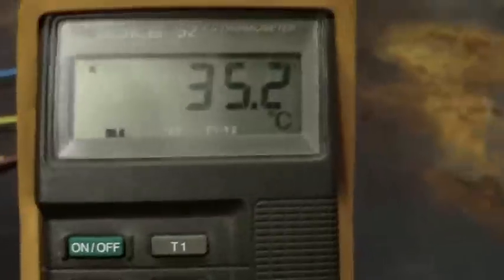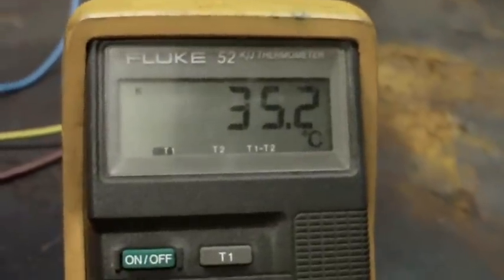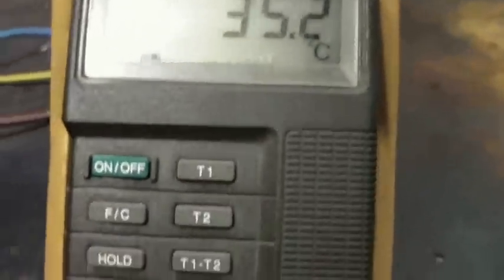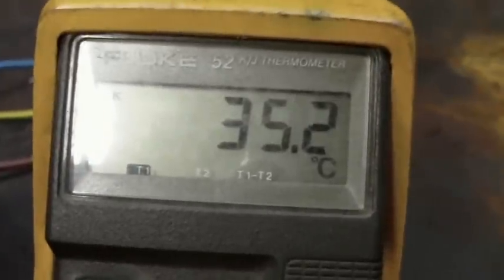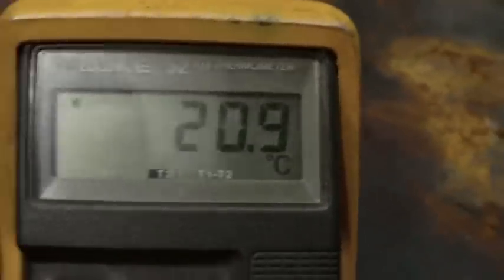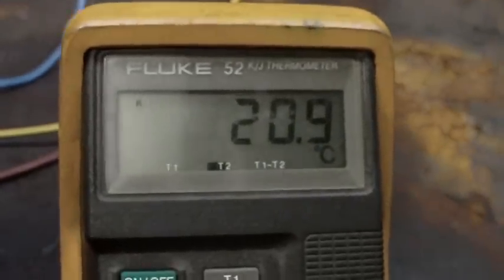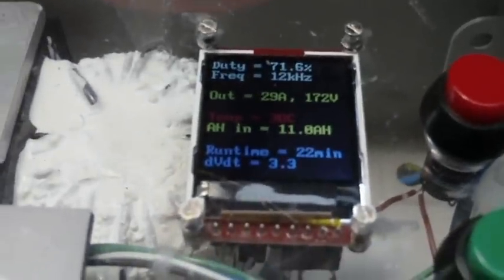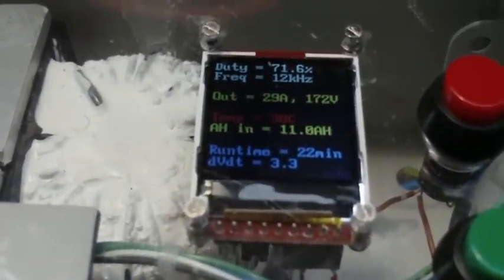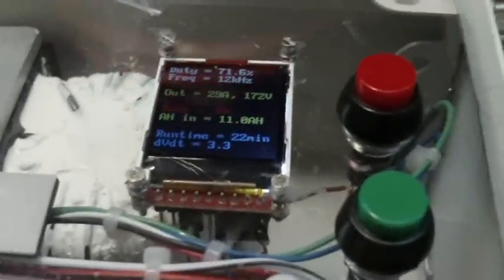This temperature probe here is on the IGBT base plate, and this one if I select T2, that's on the radiator. And the actual probe here on the charger is actually on the inductor, which is currently at 38 degrees centigrade.